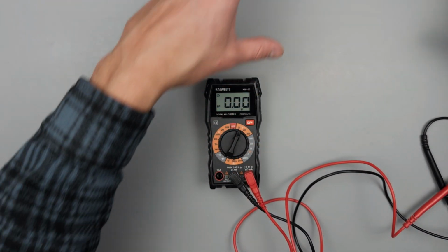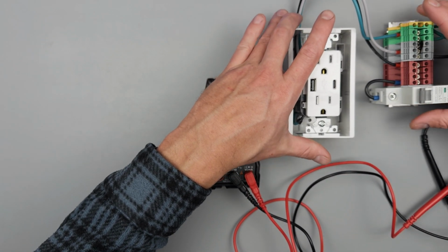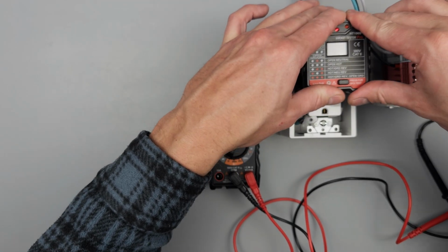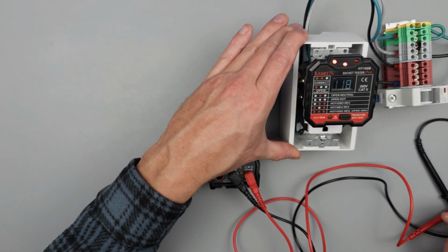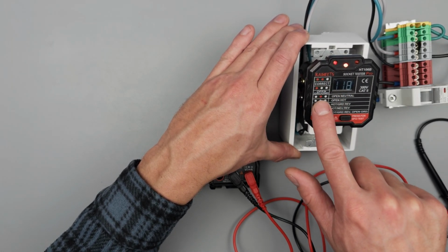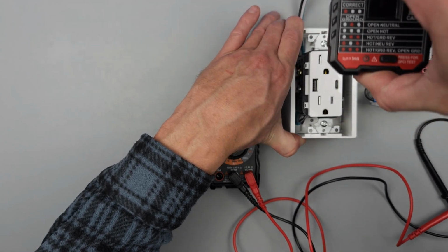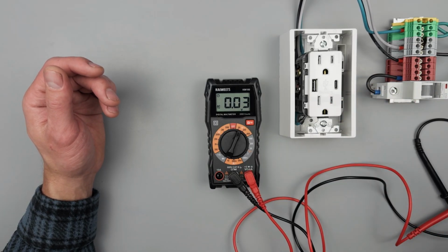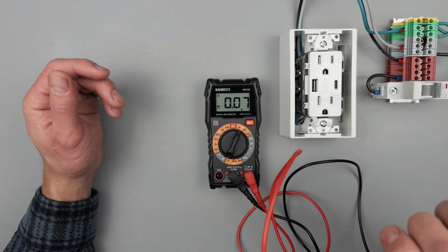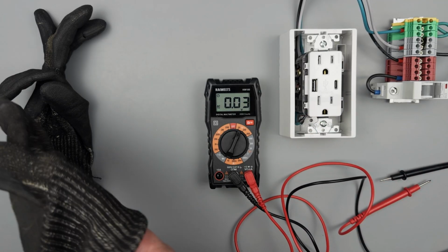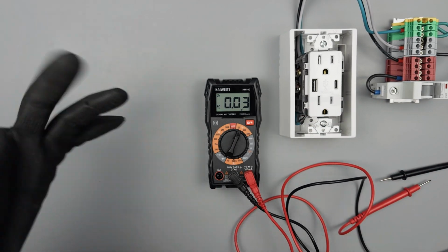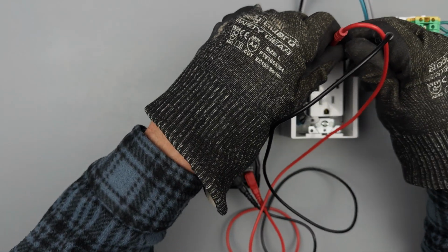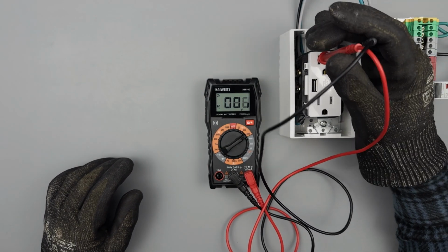Our scenario is that we have an outlet here that we would like to measure. Now, I would always recommend using an outlet tester, such as this one, and this will tell you the voltage, and it will tell you the wiring, and whether it's in the correct orientation, or terminated correctly, excuse me. But if we just have a meter, we can also measure this outlet. Now, I'm not a big fan of digging probes down into outlets, but if that's all you got, I would wear gloves and safety glasses. I like to start with the biggest setting, so I'm gonna set it to 600 volts AC. Put my probes down in here till I get a measurement.